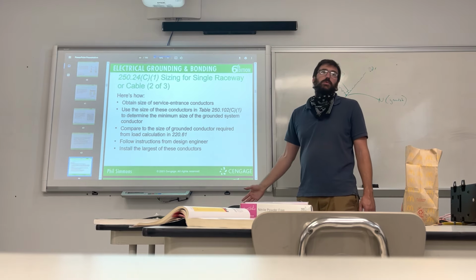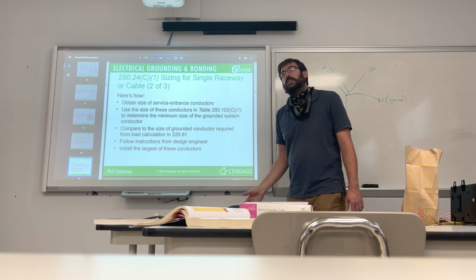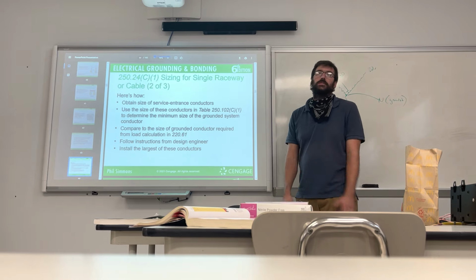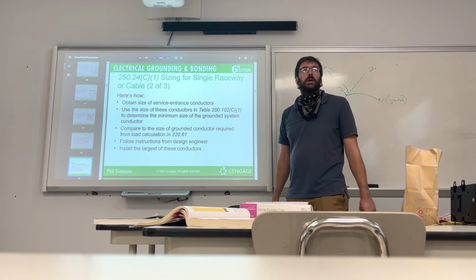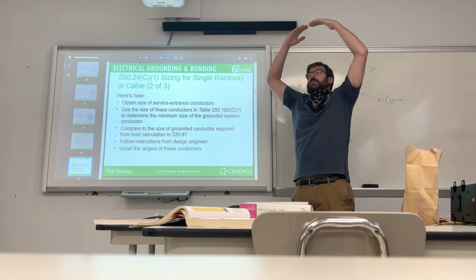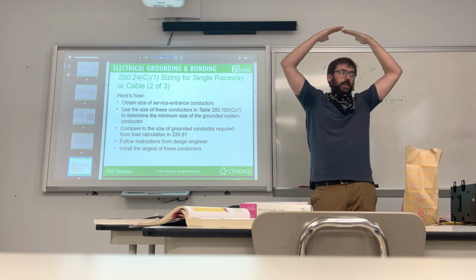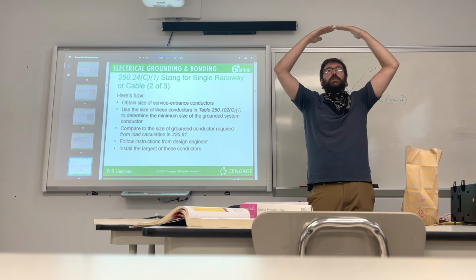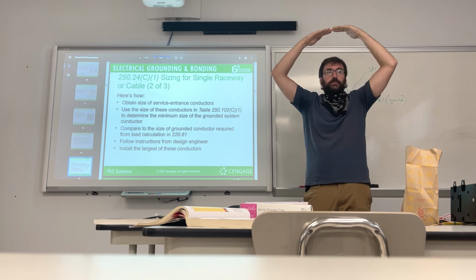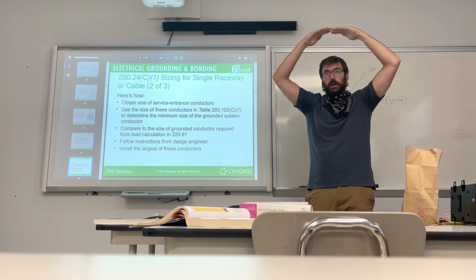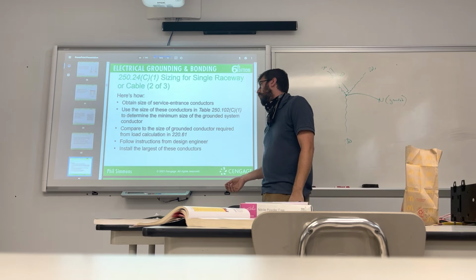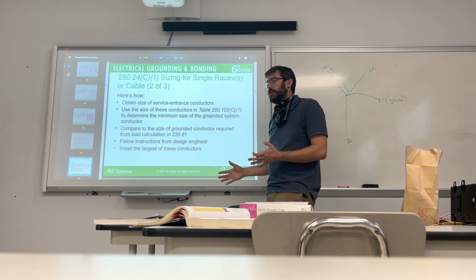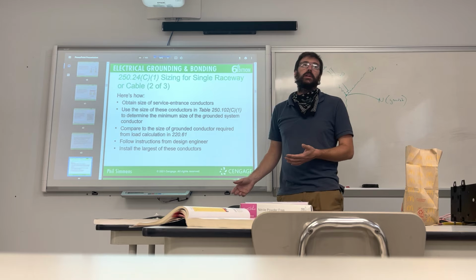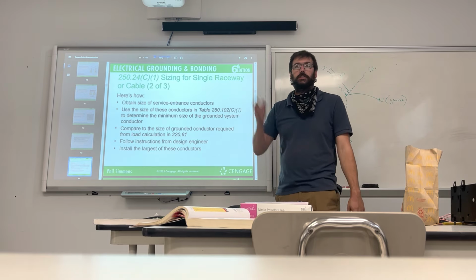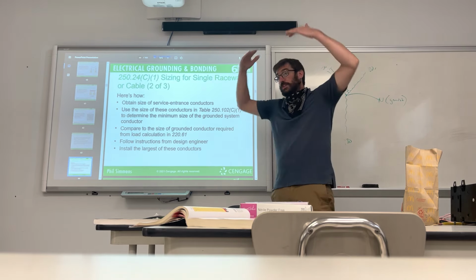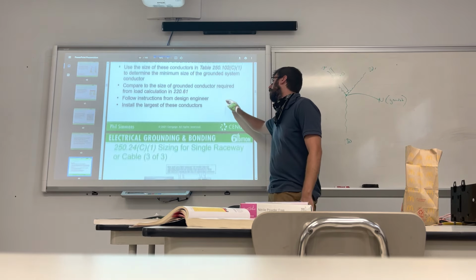Now, the rule is that if the wire goes beyond what that table can offer, you have to do 12.5% of the wire coming in. So if that wire was yay big around, I'm talking huge, let's just say theoretically, your ground wire would have to be 12.5% of this total area, which is a very small portion. The code tells you up to a certain point, like I think anything after a 4,000 amp service, they might just say, okay, it's 12.5% of whatever is coming in. So just so we know that rule too.